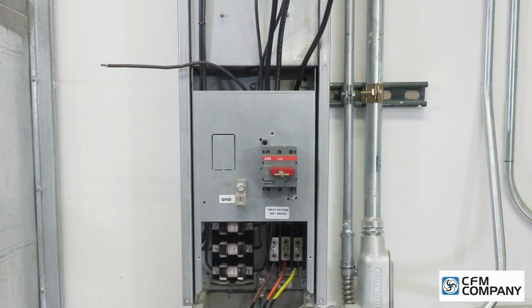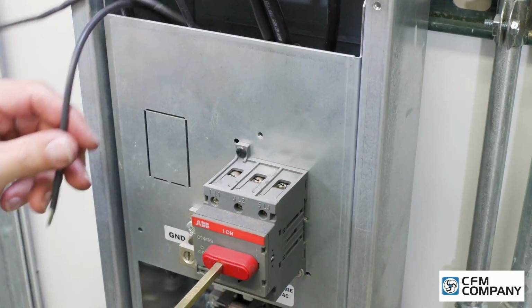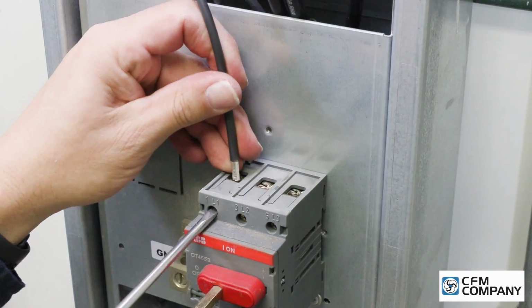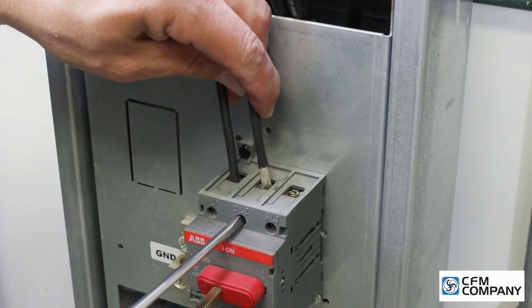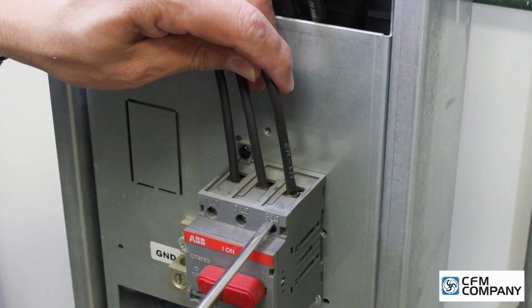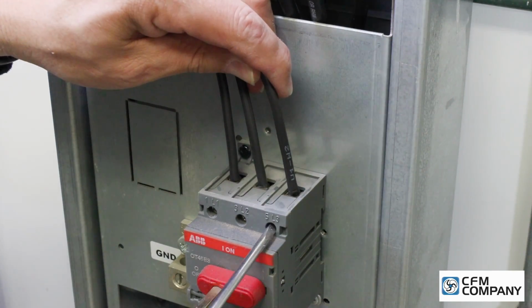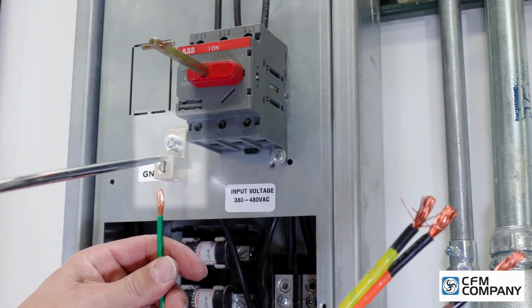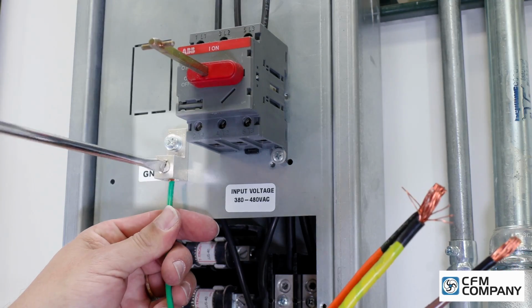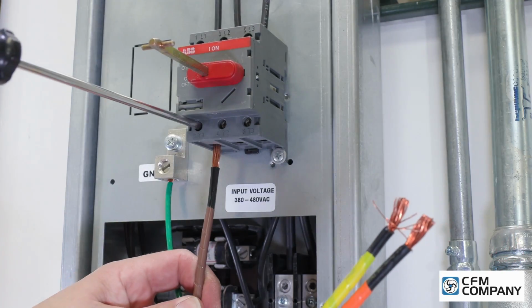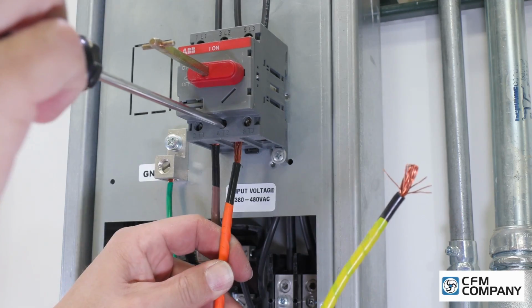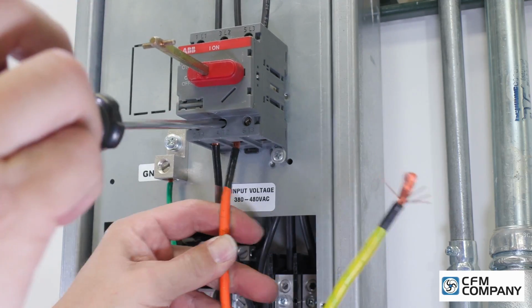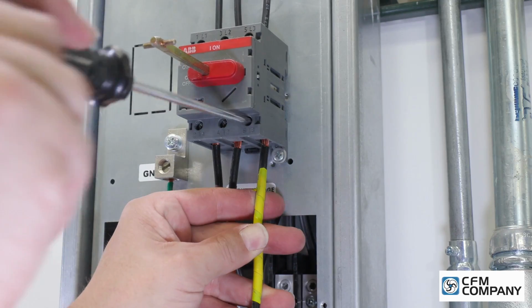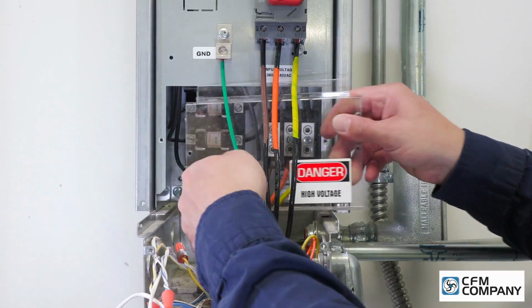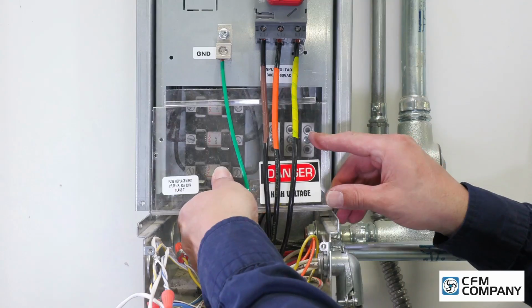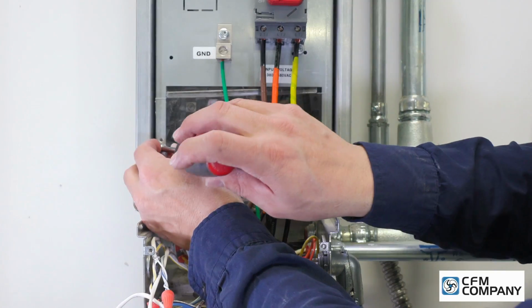With the front disconnect plate installed and secured, the 3-phase power wires from the fuse block should be pulled over the top of the plate. Connect the 3-phase power wires from the fuse block to the load side of the main disconnect. Next, connect the main ground wire to the ground lug on the front disconnect plate, and connect the main 3-phase line side power wires to the bottom of the disconnect. Install the plastic access shield over the fuse block and motor terminal block.